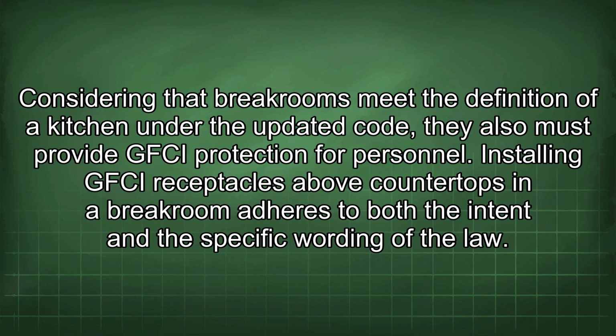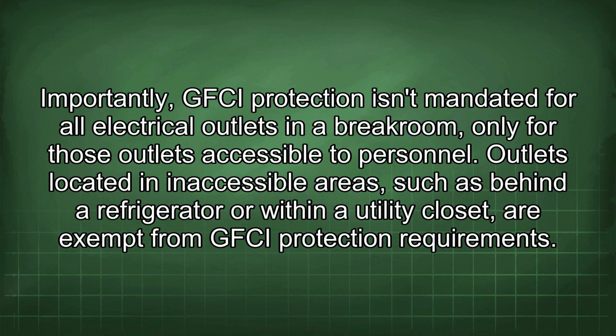Considering that breakrooms meet the definition of a kitchen under the updated code, they also must provide GFCI protection for personnel. Installing GFCI receptacles above countertops in a breakroom adheres to both the intent and the specific wording of the law. Importantly, GFCI protection isn't mandated for all electrical outlets in a breakroom, only for those outlets accessible to personnel.